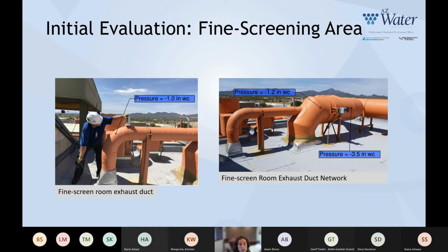And what we saw was you had only -1 inches of static water static pressure in this small channel header, but just downstream of this damper here, you can actually see that the available static pressure in that line was much, much greater. So one of our immediate improvement recommendations was to open that damper and allow more air to draw.